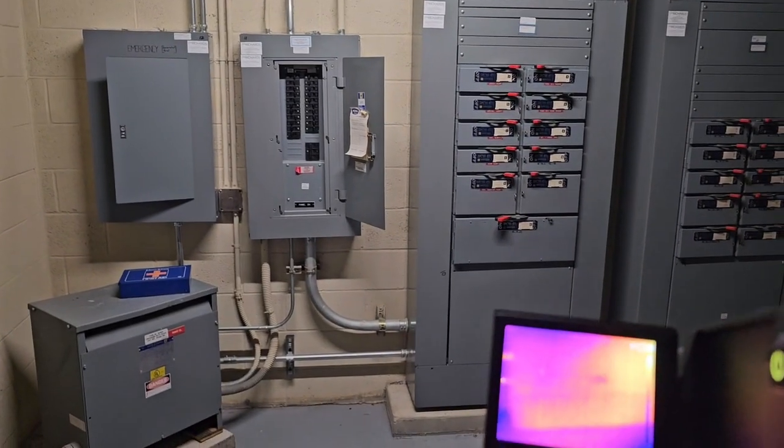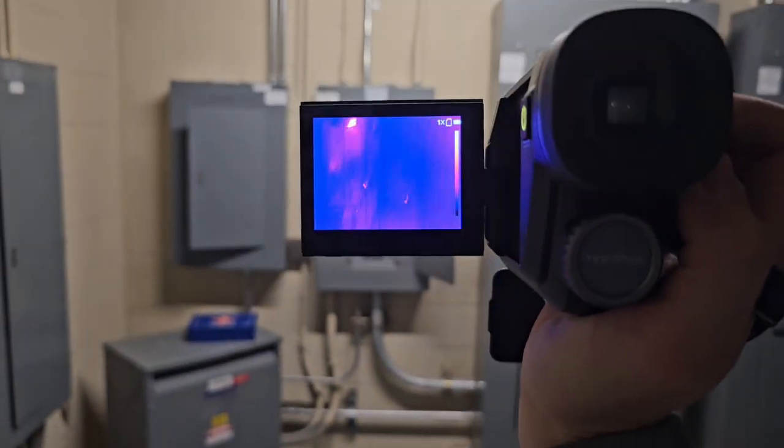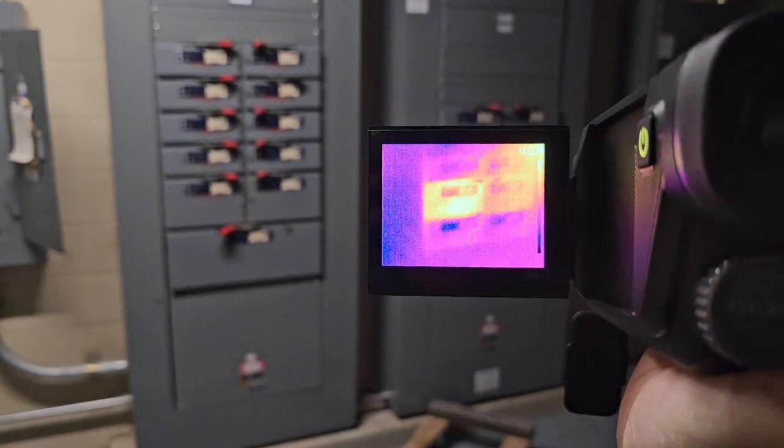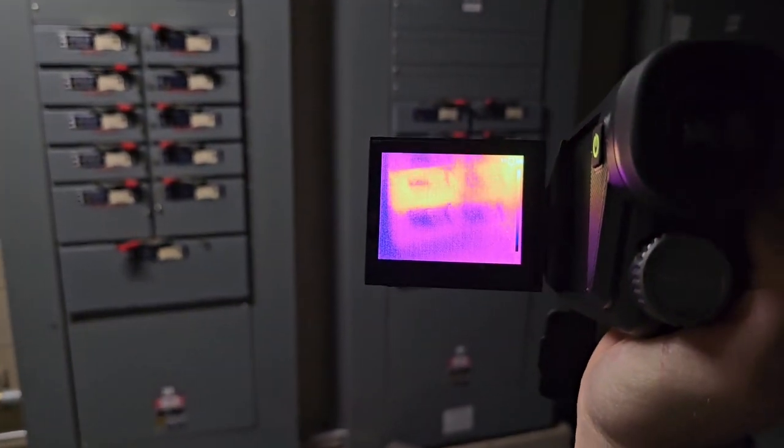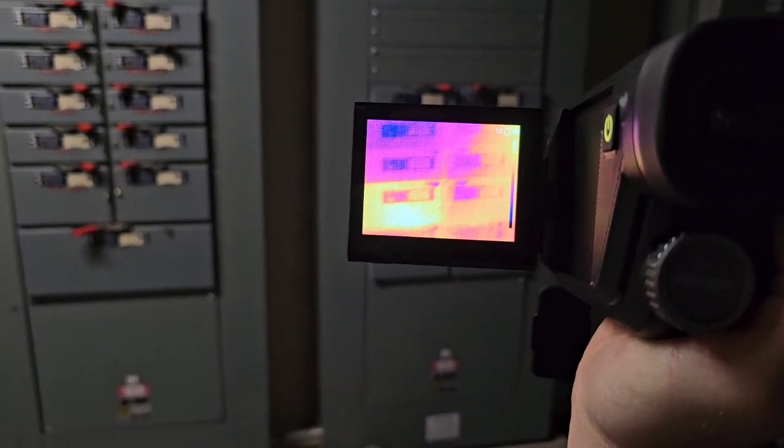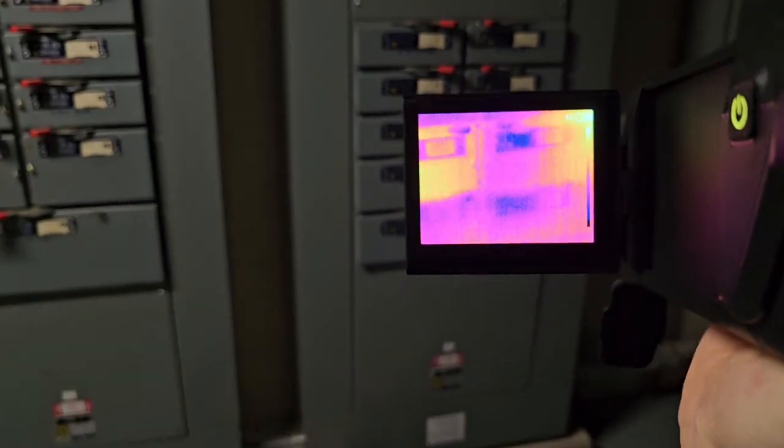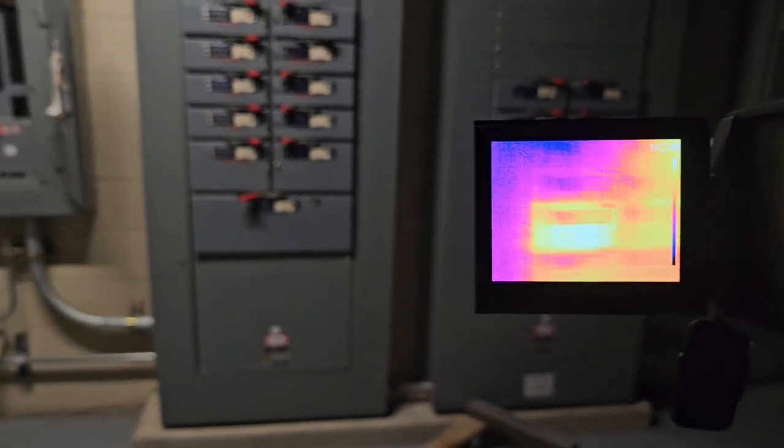Another thing you can use these thermal cameras for is going to be for inspections on circuit breakers and looking for hot spots and things like this. So we can see over here, we've got a hot spot on this one which is for some fans or something like that. So it might be something to go in and tighten up or check up.